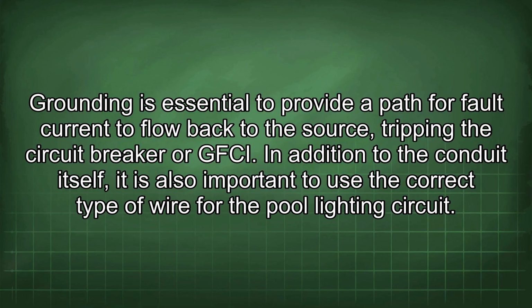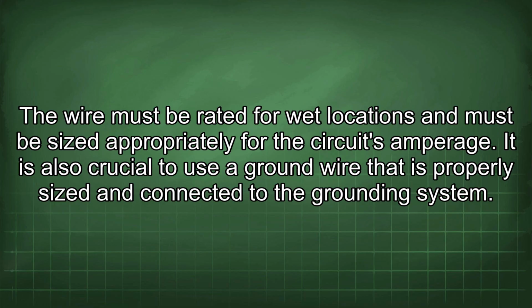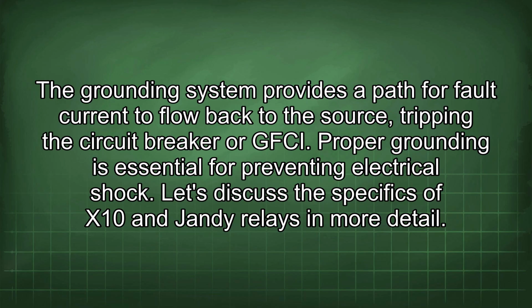or GFCI. In addition to the conduit itself, it is also important to use the correct type of wire for the pool lighting circuit. The wire must be rated for wet locations and must be sized appropriately for the circuit's amperage. It is also crucial to use a ground wire that is properly sized and connected to the grounding system. The grounding system provides a path for fault current to flow back to the source, tripping the circuit breaker, or GFCI. Proper grounding is essential for preventing electrical shock.